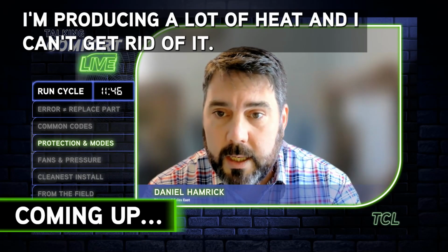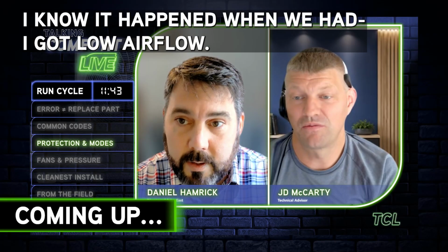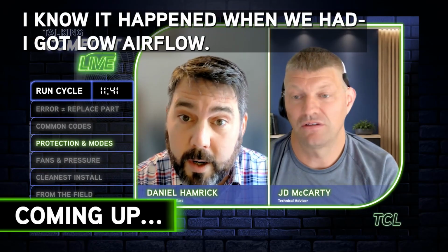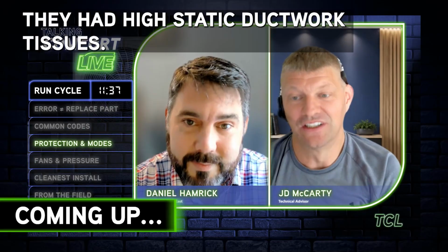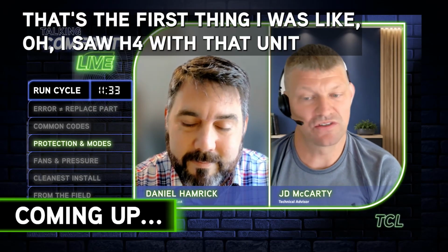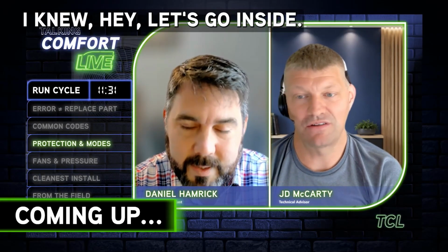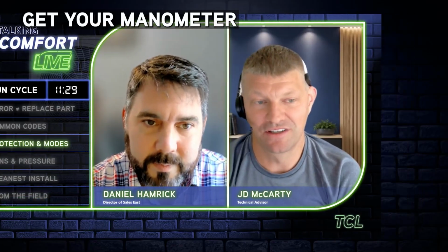I'm producing a lot of heat and I can't get rid of it. Well, I know what happened. We had low airflow. They had high static, ductwork issues. That's the first thing. As soon as I saw H4 with that unit, I knew, hey, let's go inside, get your manometer.